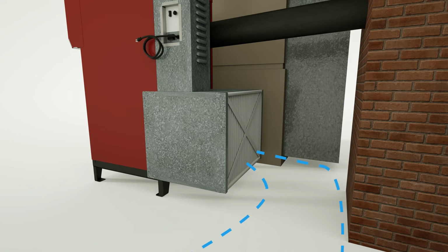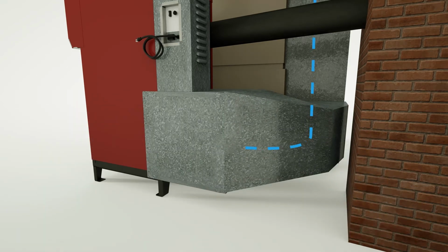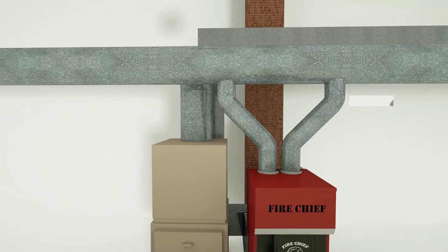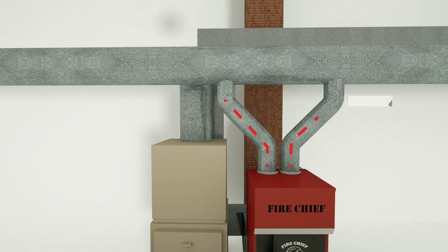If you have existing ductwork in your home, the best solution would be to connect the air filter box to the existing return air duct. This allows you to pull cold air from your home and will provide comfort throughout. When connecting the furnace to the existing return air duct, it is critical to make sure the return air is not pulling the heated distribution air back through the existing furnace. This short cycling will prevent the warmed air from being distributed throughout your home.